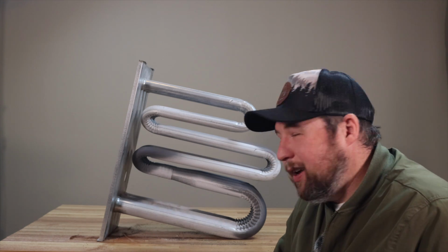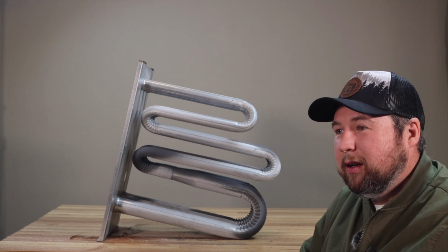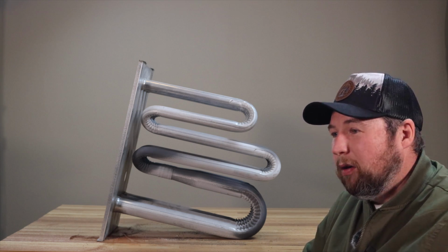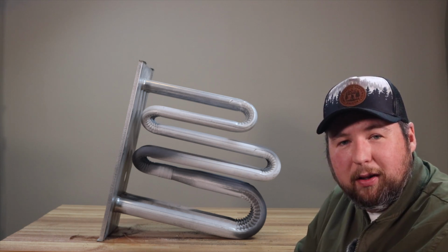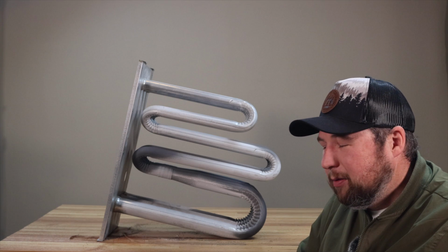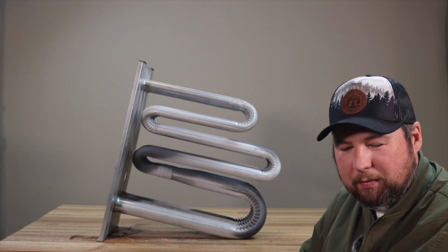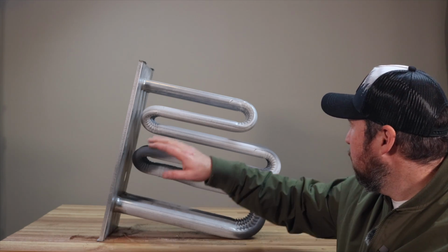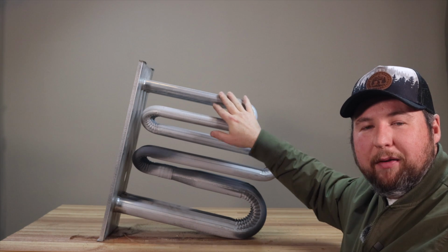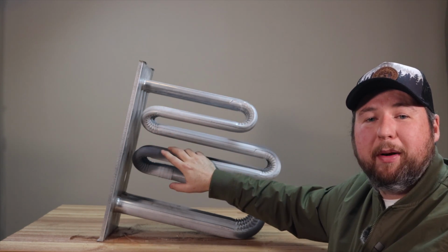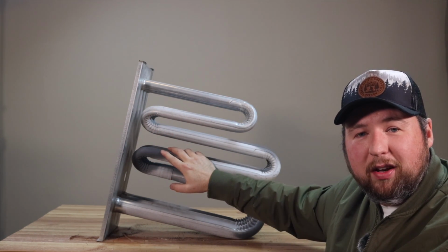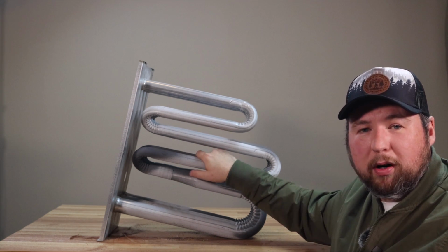Anything lower than that, you probably have your returns too small, or the homeowner wasn't changing their filters regularly. You've got a dirty blower, airflow problems. Could be a lot of different things. But what we're looking for is to make sure that we don't have a compromised heat exchanger. So what is a compromised heat exchanger? Well, it's generally going to be a hole or a crack.